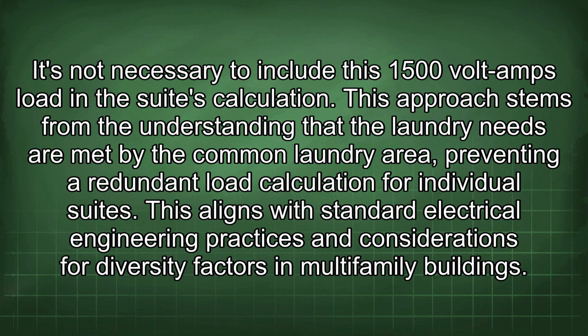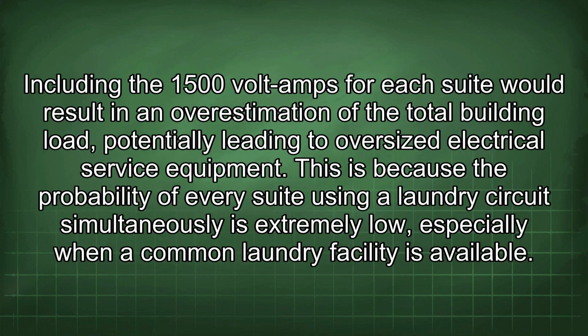This approach stems from the understanding that the laundry needs are met by the common laundry area, preventing a redundant load calculation for individual suites. This aligns with standard electrical engineering practices and considerations for diversity factors in multifamily buildings. Including the 1500-volt amps for each suite would result in an overestimation of the total building load, potentially leading to oversized electrical service equipment. This is because the probability of every suite using a laundry circuit simultaneously is extremely low, especially when a common laundry facility is available.